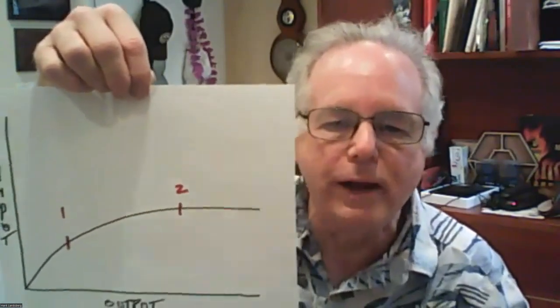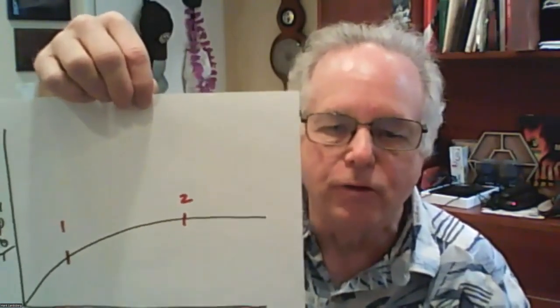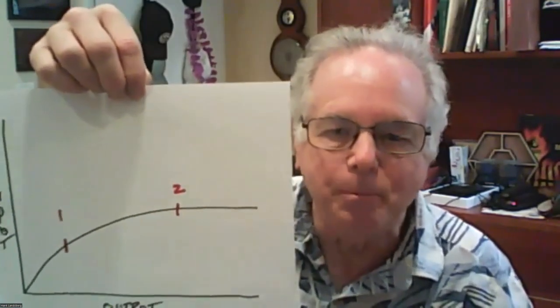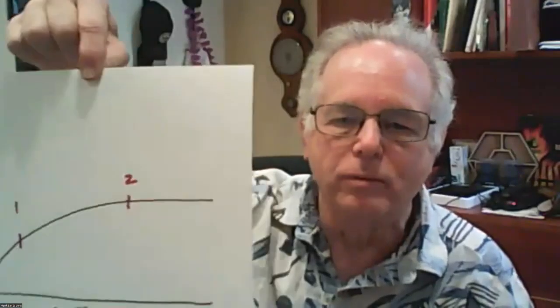And it only responds to really high voltage spikes, but it ignores the 50 to 100 volt spikes that happen all the time. So it's not a one size fits all kind of thing. So what we do in the power clamp design is that we have two separate circuits that are independent of each other. We have MOVs, which handle the lightning induced stuff, and we set the MOV threshold high enough so they only respond when the spike gets way up there, at least 1,000 volts above normal. But we set it high enough so that it's not conducting with normal line voltage, so it doesn't degrade the MOVs. They can sit there for 10 or 20 years and they're still just as effective as when they were new.